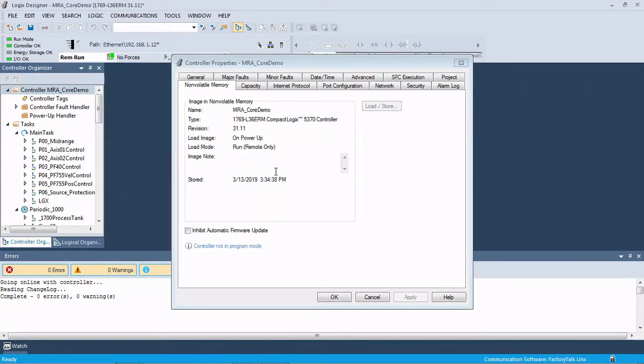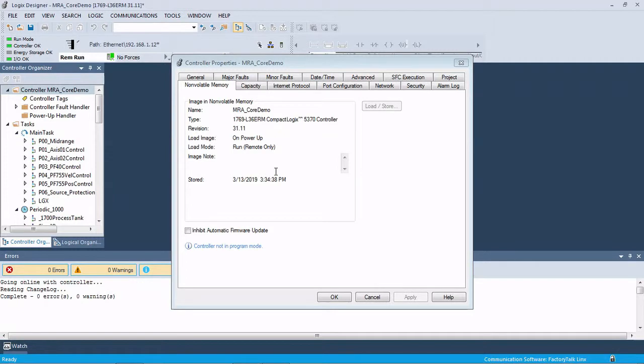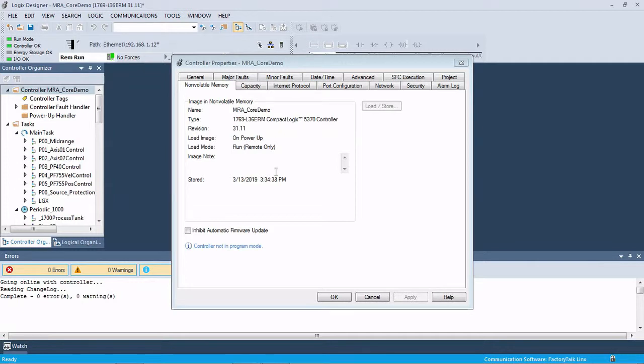We can go ahead and put our processor back in run mode. And now we can take the SD card out of the processor, put it away somewhere. We could leave it in the processor. Just every time, a reminder, every time that processor reboots, this image of the program is going to be loaded. So if any changes are made or anything, it's going to overwrite those changes. So every time that there's a change made, you want to make sure that you repeat this process. So then whatever you're going to do with the SD card, whether take it out and put it away somewhere for safekeeping or leave it in the processor is fine. It's just kind of a preference.